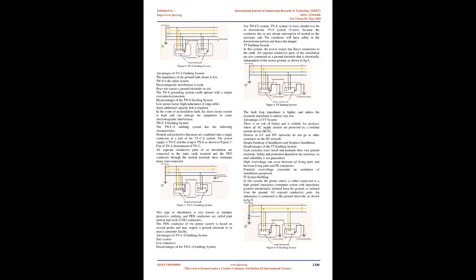Advantages of TN-S earthing system. The impedance of the ground fault circuit is low. TN-S is the safest system. Electromagnetic interference is weak. Does not require a ground electrode on site. The TN-S grounding system could operate with a simple overcurrent protection. Disadvantages of the TN-S earthing system. Low power factor, high inductance of long cable. Same additional capacity link is required. In the event of an insulation fault, the short circuit current is high and can damage the equipment or cause electromagnetic interference.